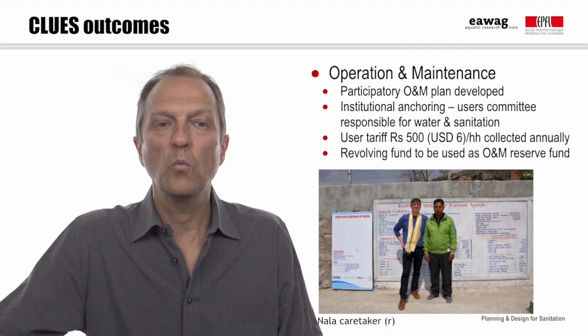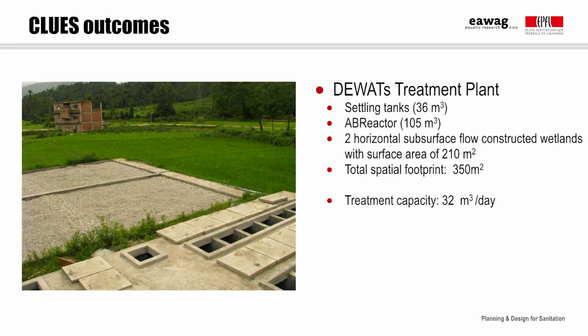a new household. The infrastructure that was put in place in Nala includes a state-of-the-art DEWATS treatment plant, including 36 cubic meter settling tanks, 2 ABR reactors with 105 cubic meter volume, and, shown on the left in the background, 2 horizontal subsurface flow constructed wetlands with a surface area of 210 square meters. This is during the construction phase, and that is why the constructed wetlands have not yet been planted. The entire spatial footprint of the plant is 350 square meters. The overall treatment capacity is designed for 32 cubic meters per day.